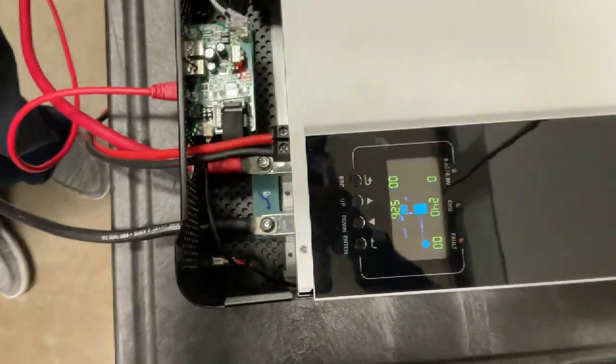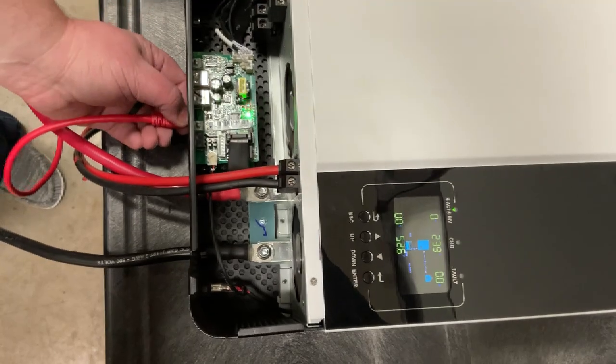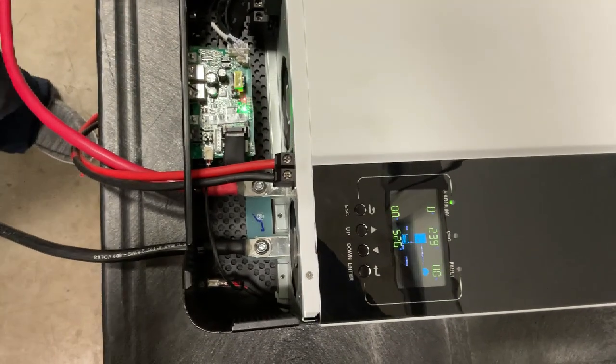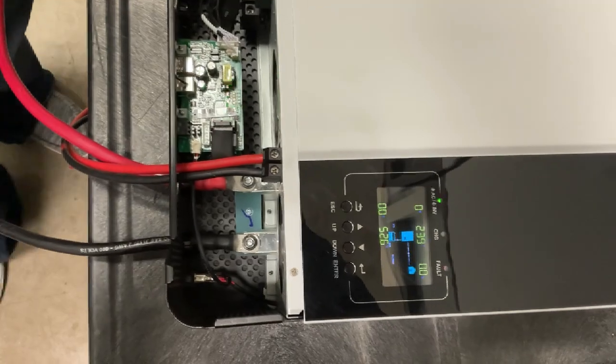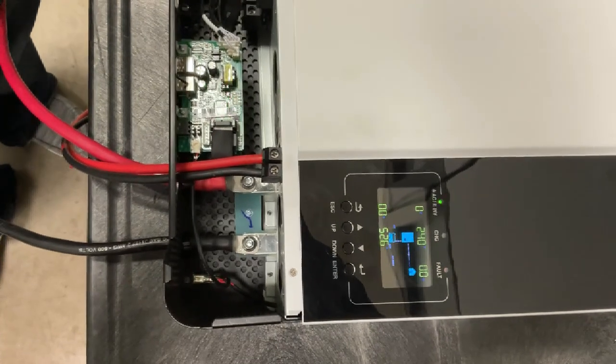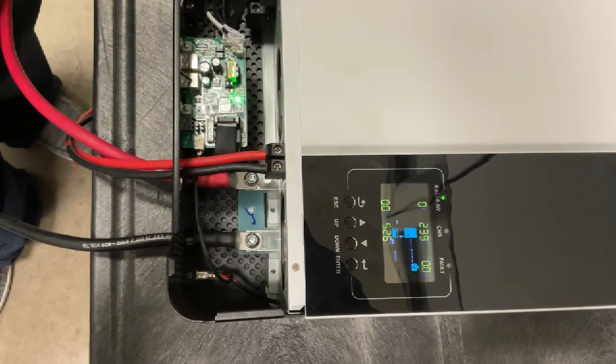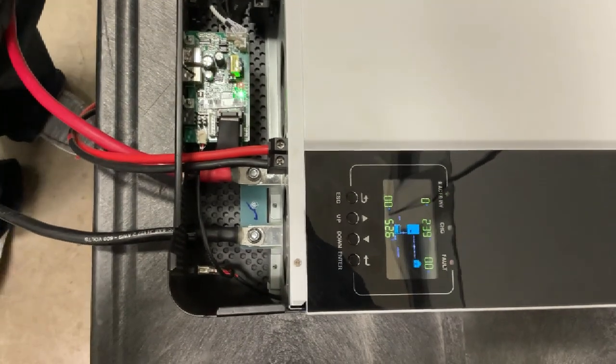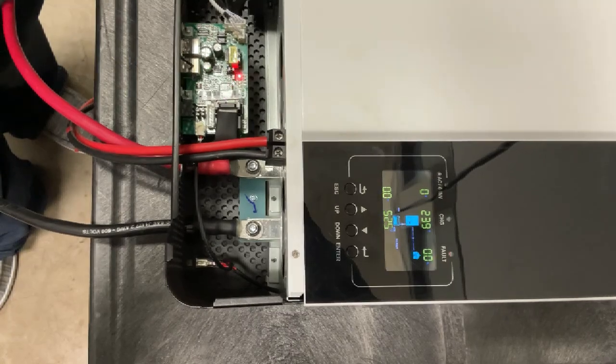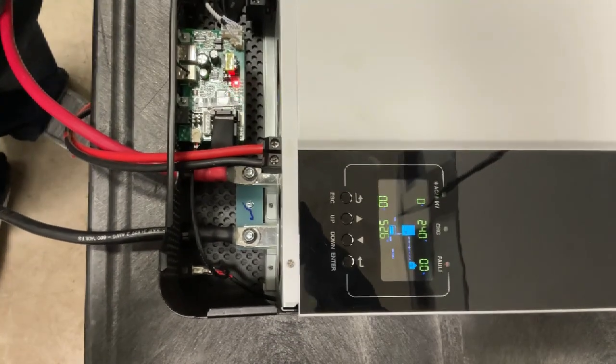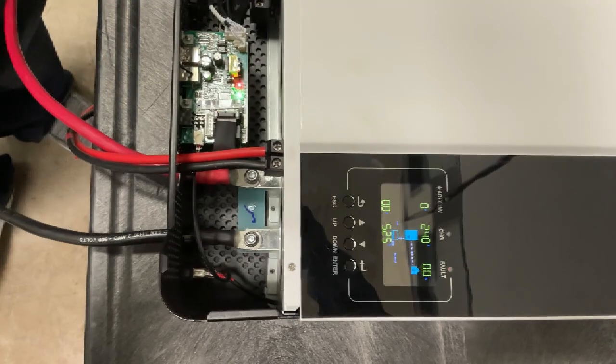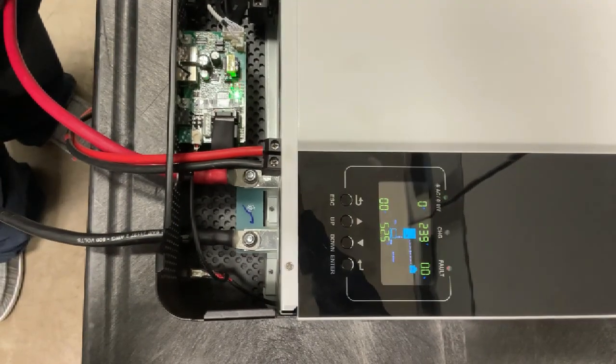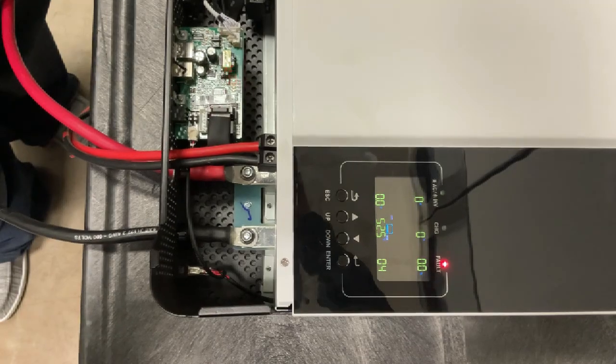...come to your inverter and unplug your BMS cable from the bottom of the inverter. Within 15 seconds, you're going to get error four and error 20. Error 20 is the inverter telling you, you have said I have a lithium battery with a BMS. I'm calling the battery and they are not answering. Error four is you have told me I have a lithium battery with BMS and I don't read any voltage. Therefore your voltages are low.